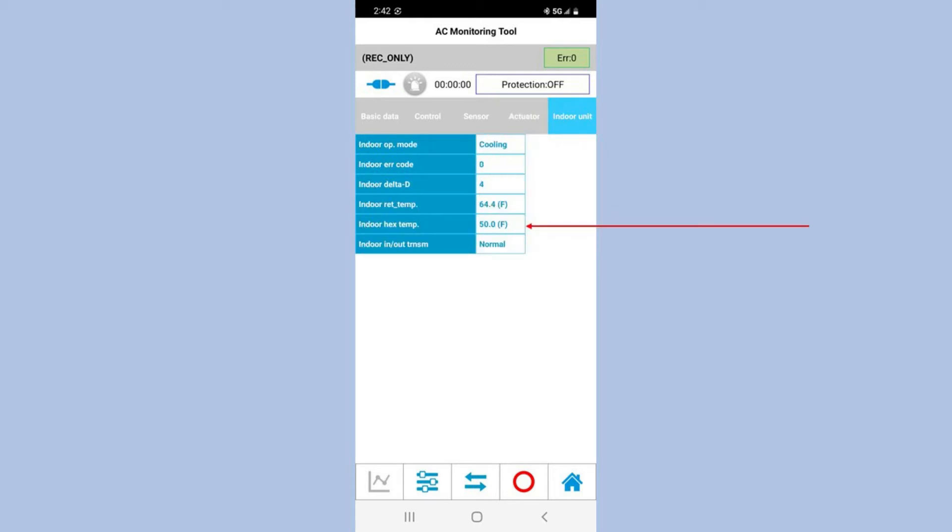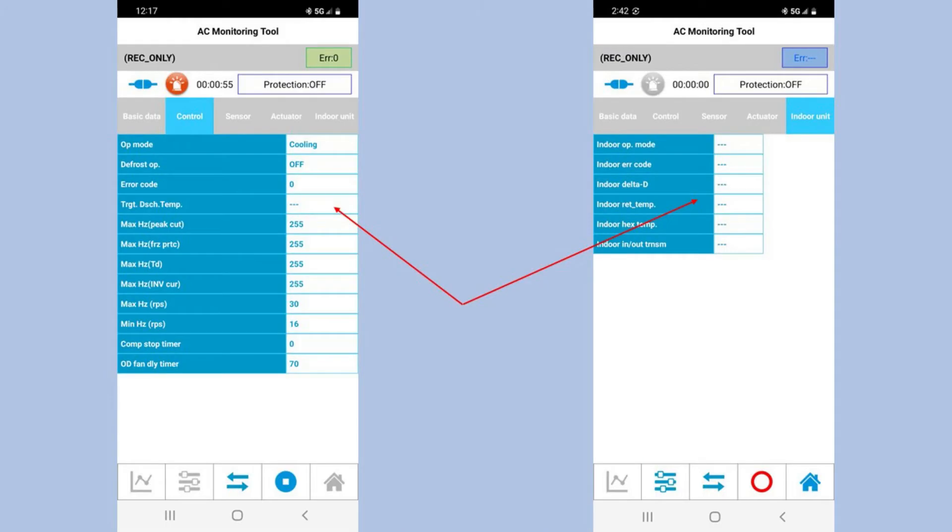So depending on the equipment, it will vary. But our indoor heat exchanger temp will vary from 42 to 47 in cooling, and 108 to 116 in heating before it starts to limit the compressor, slow the frequency down and go into a protection mode. Also, if they get too low or too high, we'll go into a safety mode and can shut the unit down. Some examples of no data appearing: don't panic. The target discharge temp on some equipment will show 32 degrees until it figures out what it wants it to be, or it'll come up blank. And you'll see on the right here it's entirely blank for the entire indoor unit. It either doesn't see it or it's cycling through a timing.